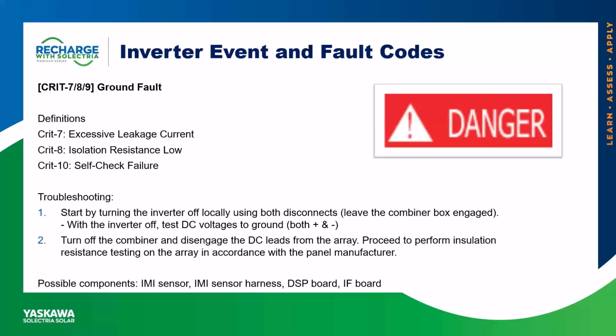There are several ground connections throughout the cabinet interior that you should inspect and verify they are properly seated when CRIT 10 occurs. Those being J23 on the DSP board, J2 on the interface board, J1 on the DC-MOV board, and J2 on the DC discharge board. The connection between the DSP and the DC discharge board, J10, if not seated properly, will result in a CRIT 10. For that matter, if any component in the circuit is unplugged, it could result in a CRIT 10 occurring.